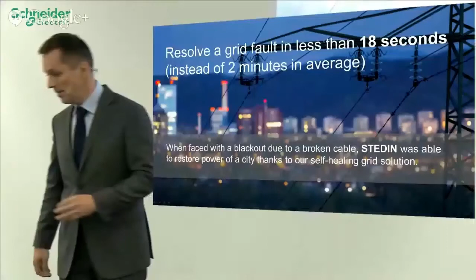Here, a cable was cut by a storm or physical incident, and the network was restored in 18 seconds. On average, this kind of restoration would have taken 2 minutes before we installed this system. So you see, we're able to operate closer to the limit of this grid, which increases the capacity of energy transiting through the grid without adding more cables and switchgear.